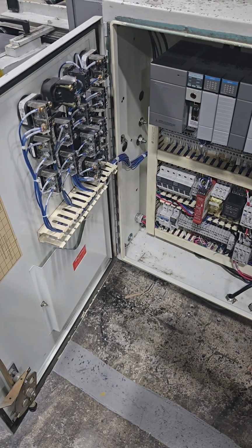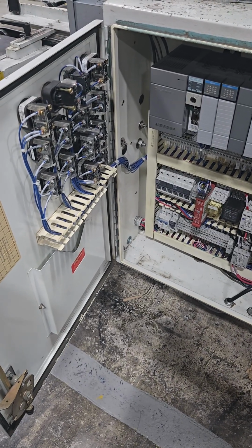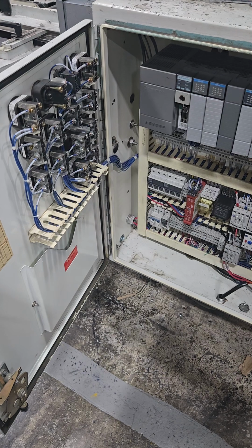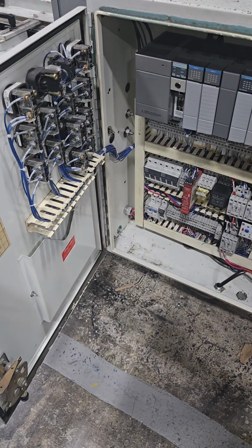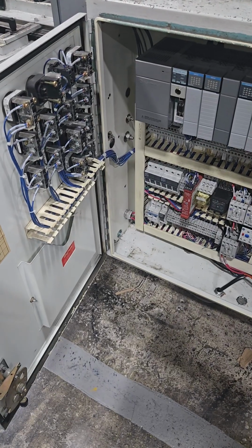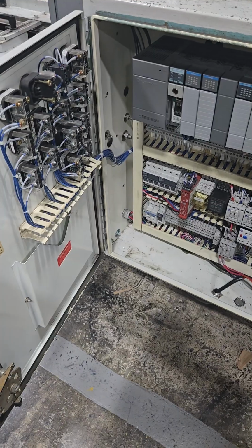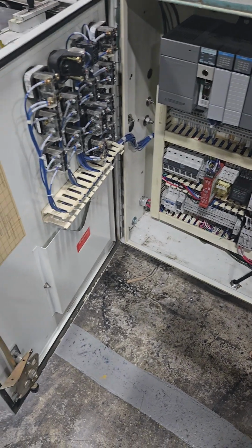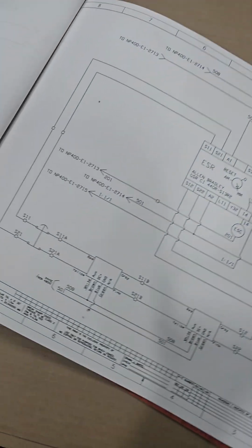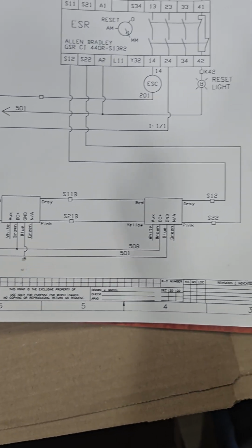And when we upgraded this ladder over here to a PLC, it is nice, but you still need to have the essential knowledge of relay logic before you can start programming. And why is that? Because relay logic forms the foundation for modern PLC programming and industrial safety systems. Many emergency stop and interlock systems still rely on relay logic for fail-safe operations to this day. Such as this example in this print, you can see that the wires are wired in series.